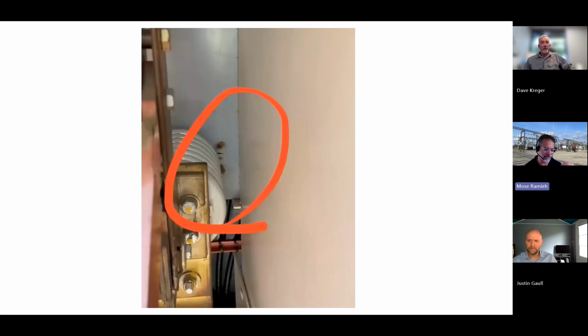If we just have enough time - this story just came to me, out of nowhere. We talk about cleanliness, and this is a little example of how even minor problems in gear can begin to cause issues. We had a customer, a steel foundry, and this is an example of how resilient electrical equipment can be, even if it doesn't get maintained. The steel dust was so thick, I had to scrape the dust away from the door with my boot just so I could open the door on the switch.